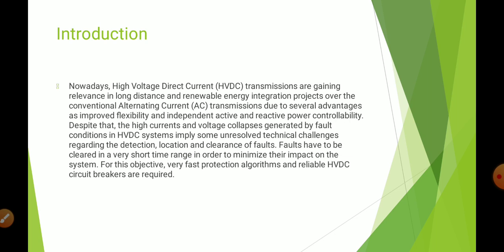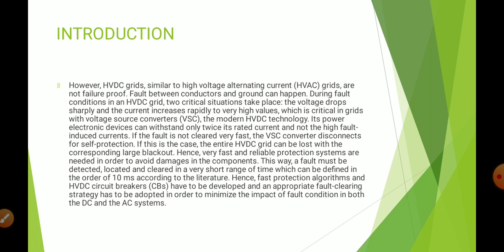Despite that, the high currents and voltage collapses generated by fault conditions in HVDC systems imply some unresolved technical challenges regarding the detection, location, and clearance of faults. Faults have to be cleared in a very short time range in order to minimize their impact, or else the impact may be higher on the system. For this objective, very fast protection algorithms and reliable HVDC circuit breakers are required. However, HVDC grids, similar to high voltage alternating current grids, are not failure proof. Faults between conductors and ground can happen anytime.